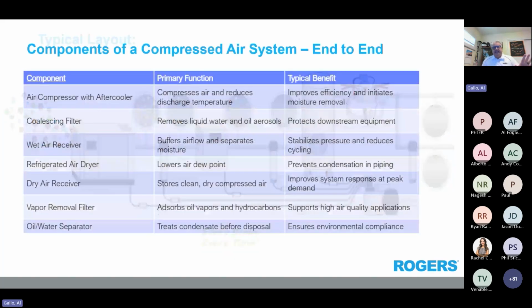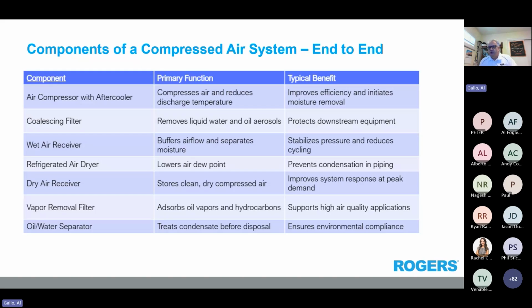This is more of just the components of the air system, and really what I wanted to achieve with this slide is the compressor is basically the first piece of the air treatment that we're going to do, because we have those aftercoolers in compressors. That aftercooler is going to start cooling the air down, get the moisture separator to work correctly before we start sending it down to the rest of the air treatment.